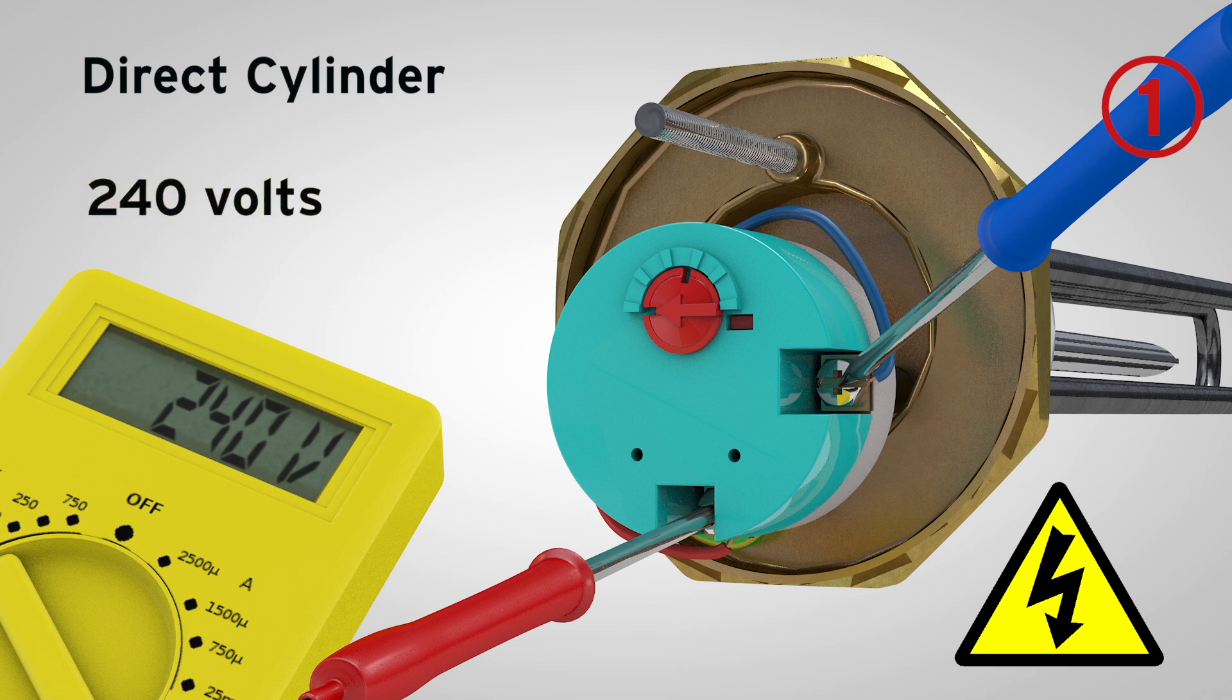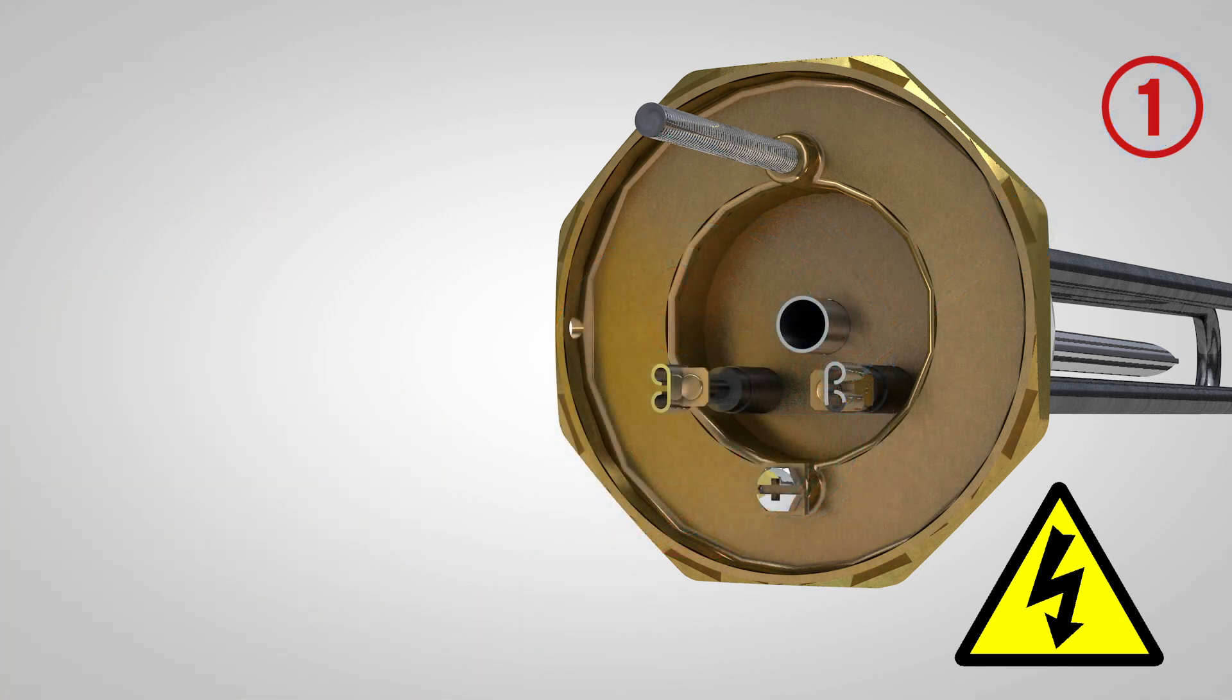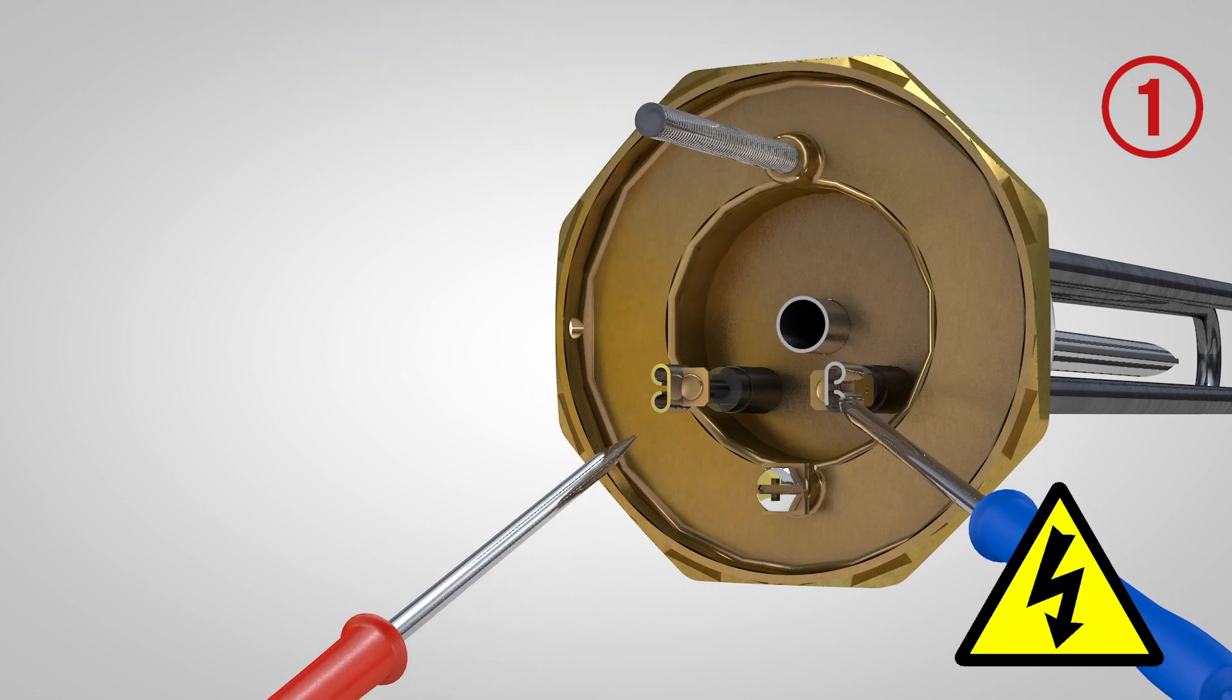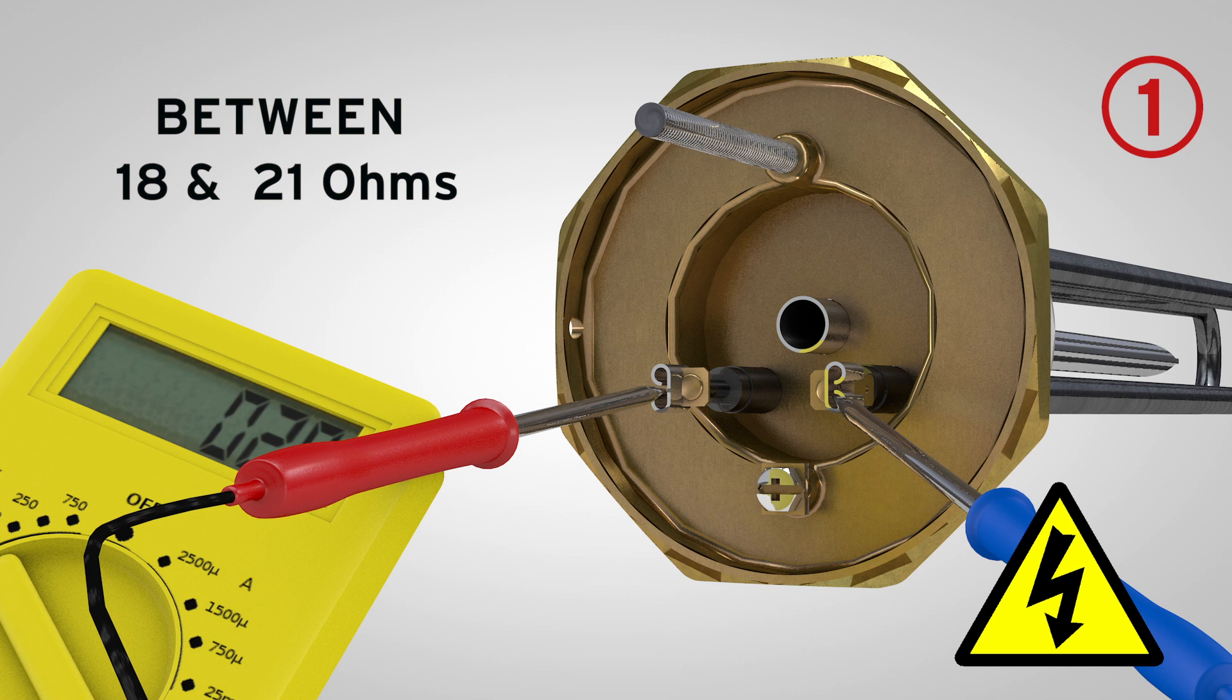If the power supply is okay, you will need to move on to check the immersion heater. You can diagnose the immersion heater has failed by measuring the resistance between the two posts on the immersion with a multimeter. The reading should be between 18 and 21 ohms, or the immersion has failed and will need replacing.